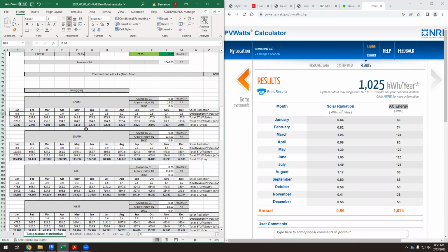In that building, we have a solar heat gain coefficient. So what does it matter if this solar heat gain coefficient is 0.6 or 0.65 or 0.64, whatever? That means that only 60% of the heat enters the building, of if this is 100. So only 60% of the sun enters the building.